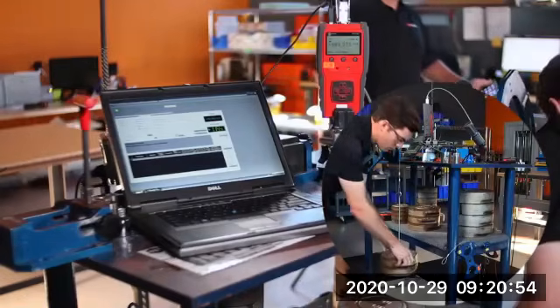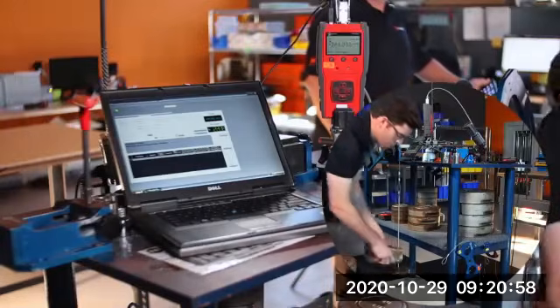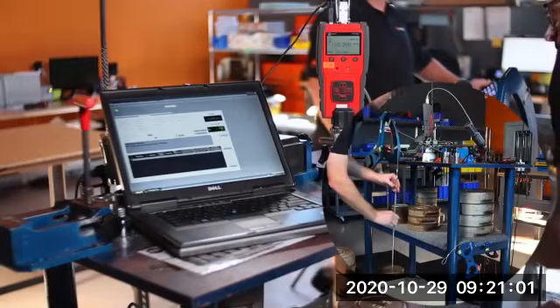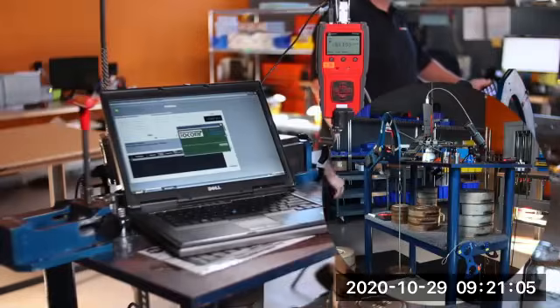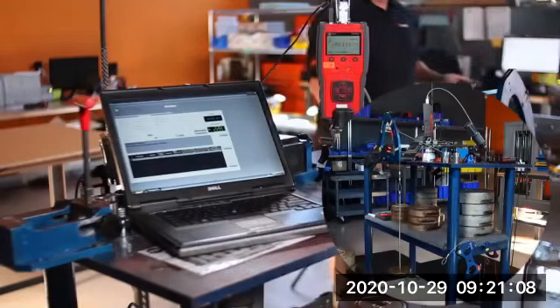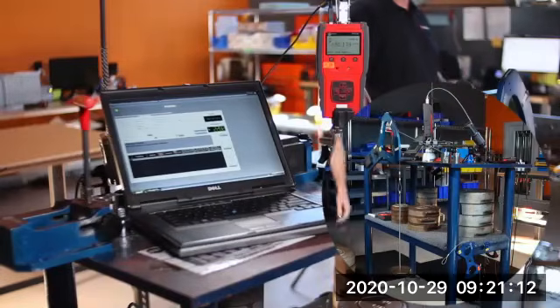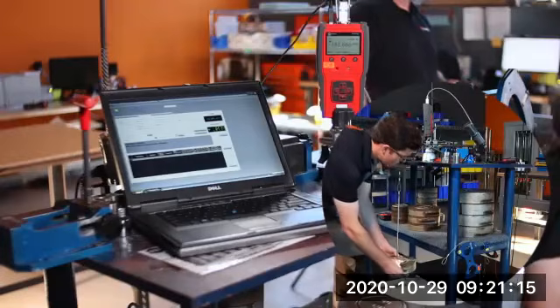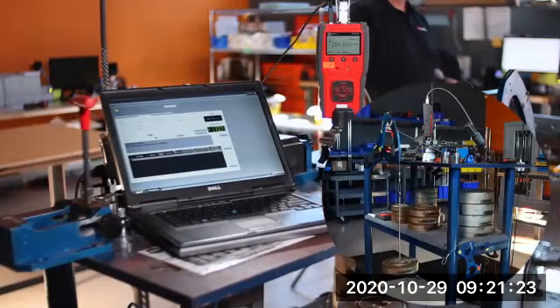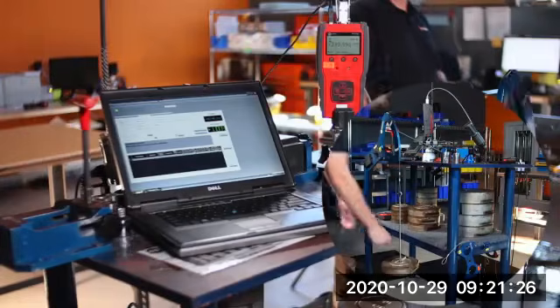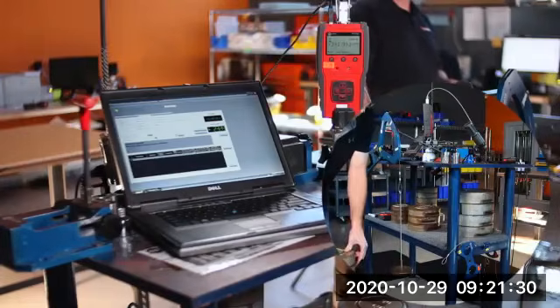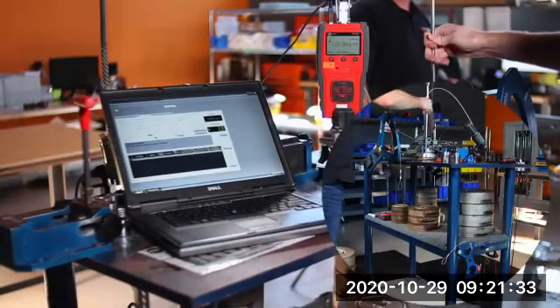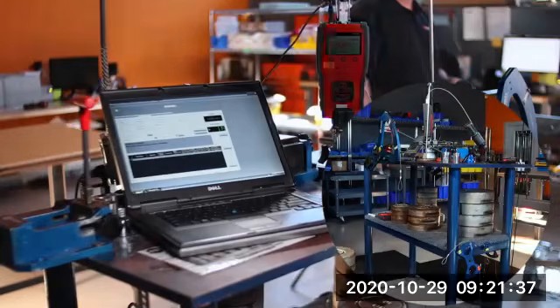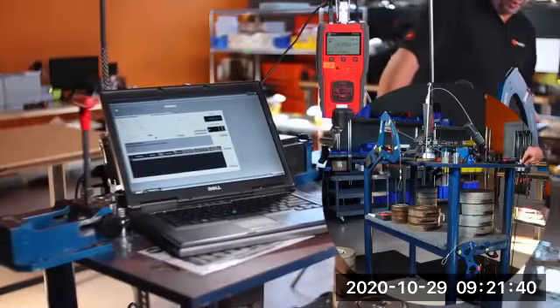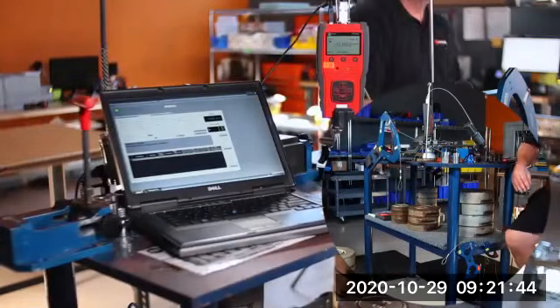And so in a typical process, the weights that are measured in the counterclockwise and clockwise directions are done a total of 3 times. The first value is taken as first presented. Then if there are any modifications that need to be made, we do one more check in those directions as well. And then after that, a final check to make sure that all of that calibration data was done correctly. And that's the process that happens for the calibration of the analyzer and the sensor.